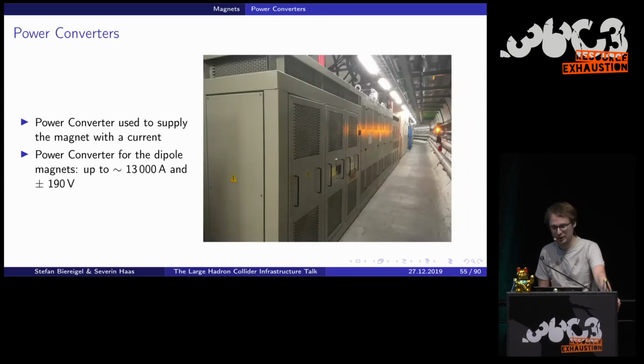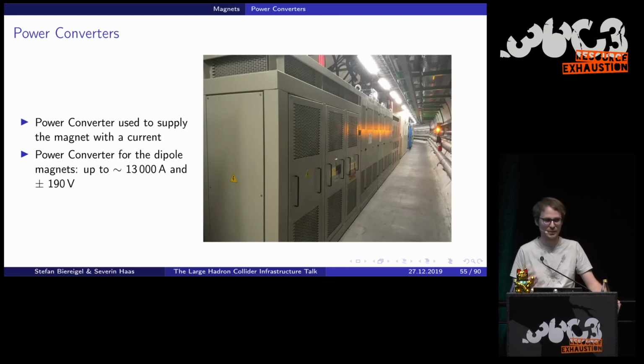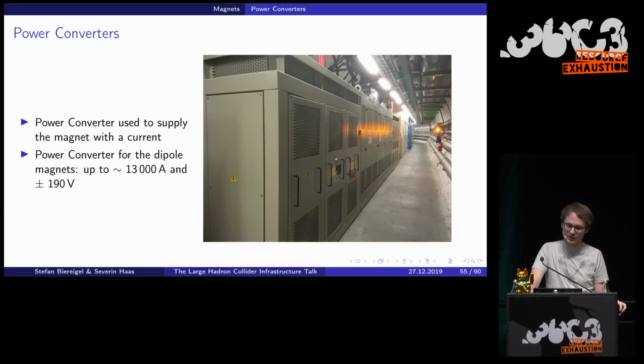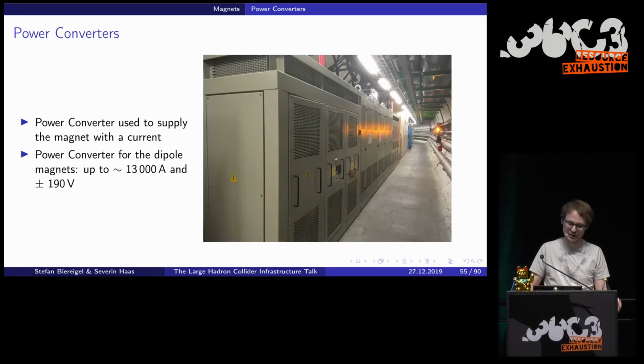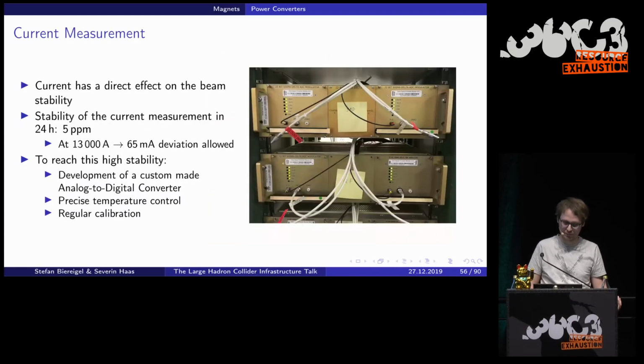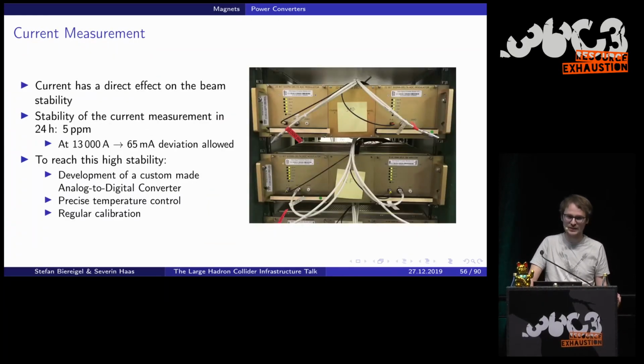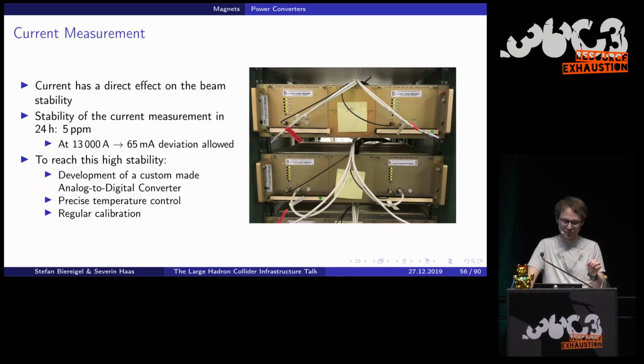Power converters. The power converters are used to power the magnet itself, so they can produce a current of approximately 13,000 amps and a voltage of plus minus 190 volts. And you can see a picture of how big it is. One difficulty with the power converters is that they have to be very precise, because every instability in the current has a direct effect on the beam stability itself. The beam would not be diverted by the right amount. That's why they have to have a very precise stability.